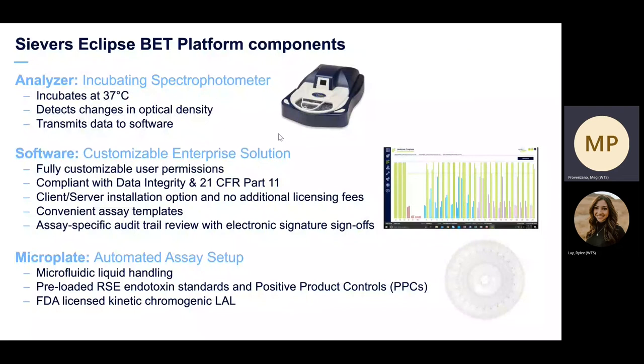The platform components consist of an incubating spectrophotometer, which can incubate at 37 degrees C. It can detect the change in optical density similar to other microplate readers, and then it transmits the data to software. The software is a customizable enterprise solution with fully customizable user permissions. It's compliant with data integrity and 21 CFR Part 11 and also offers a server installation option — you could have a lab computer with the software on it and also a manager or office computer with the client installed directing to the same server, allowing for easy sign-offs and audit trail review with electronic signatures.